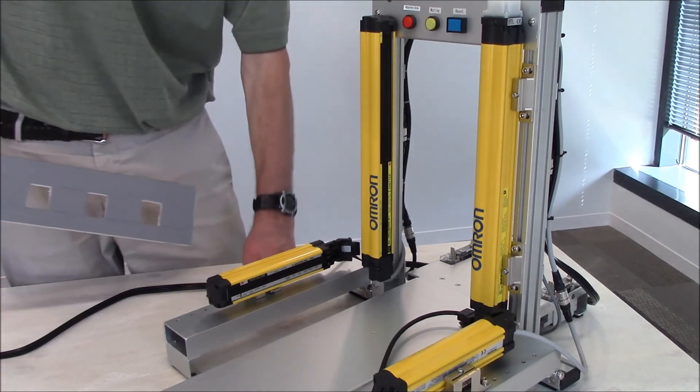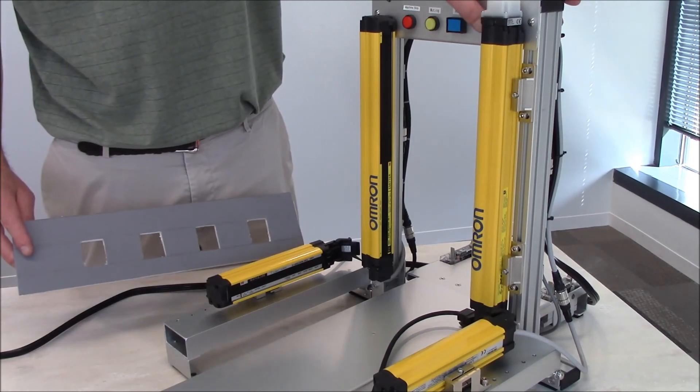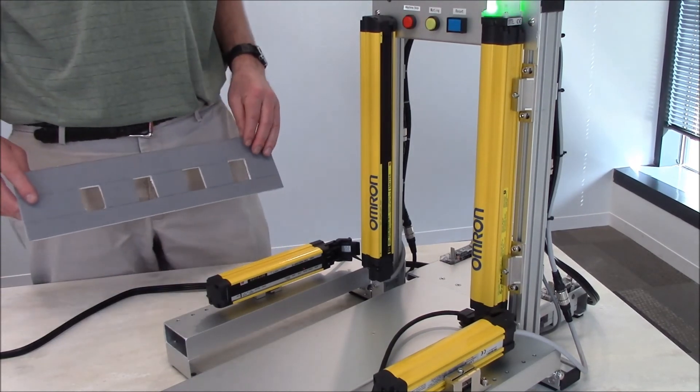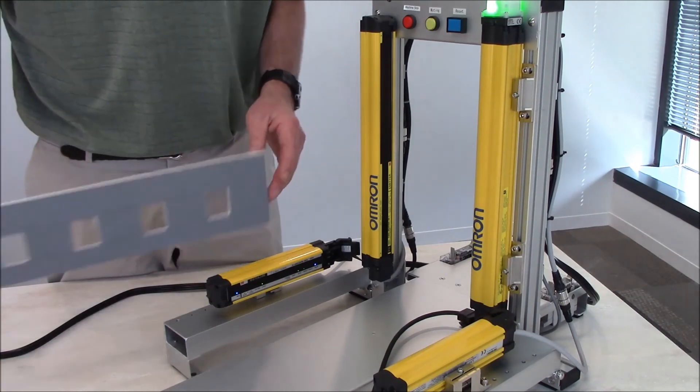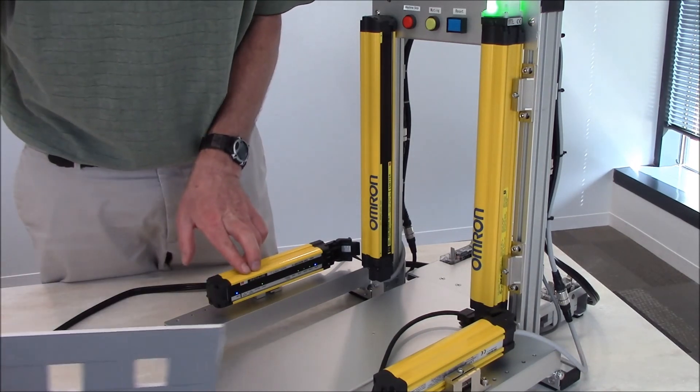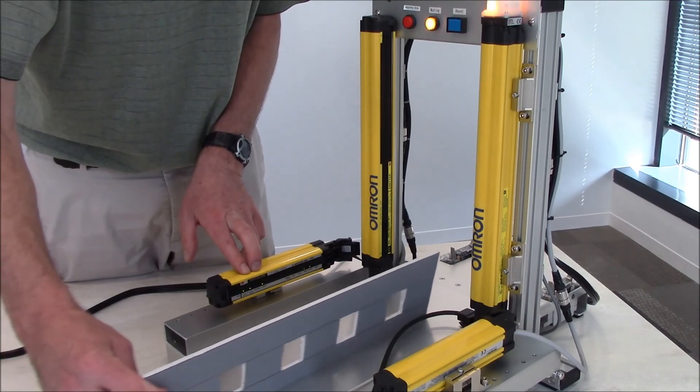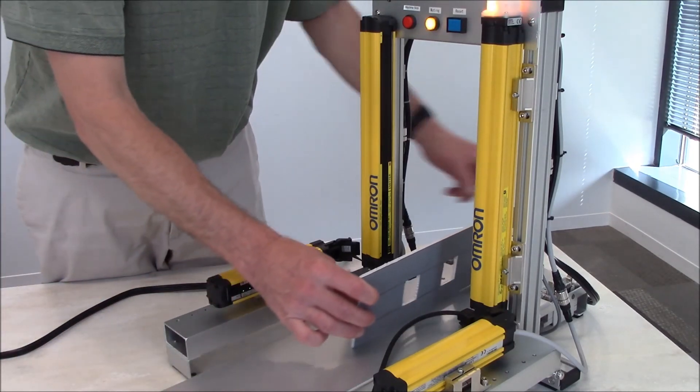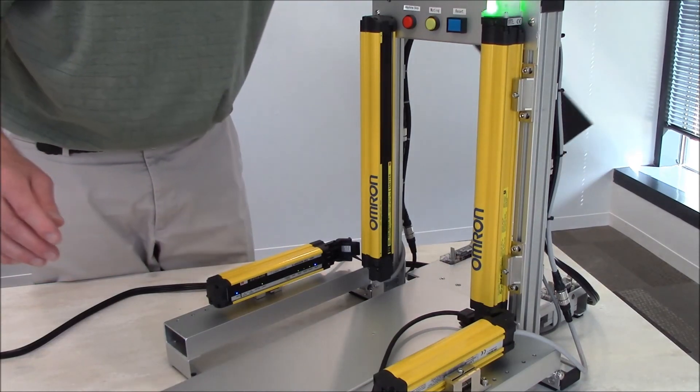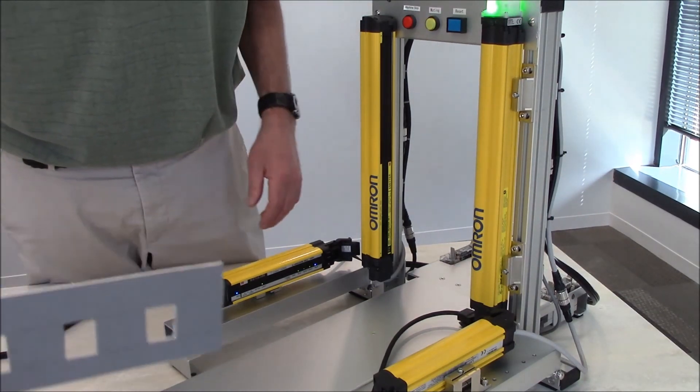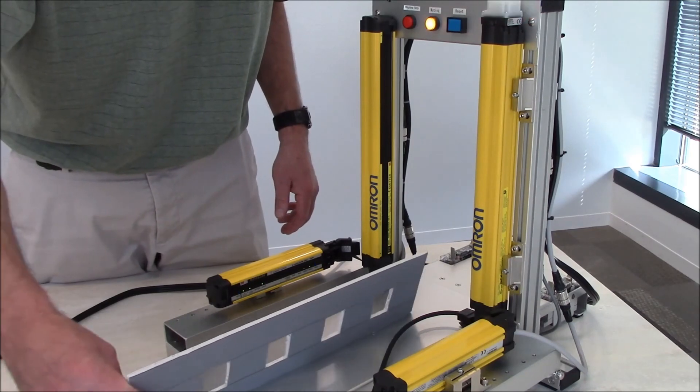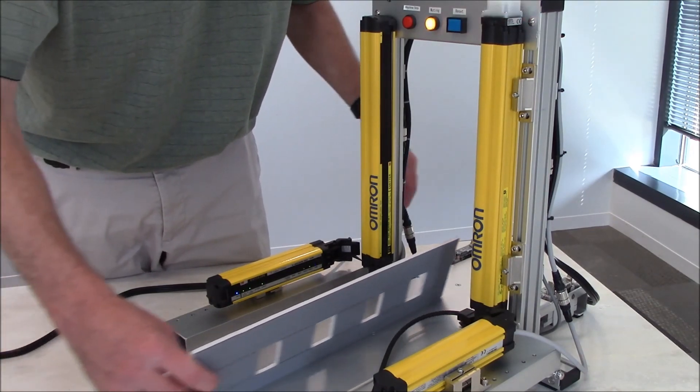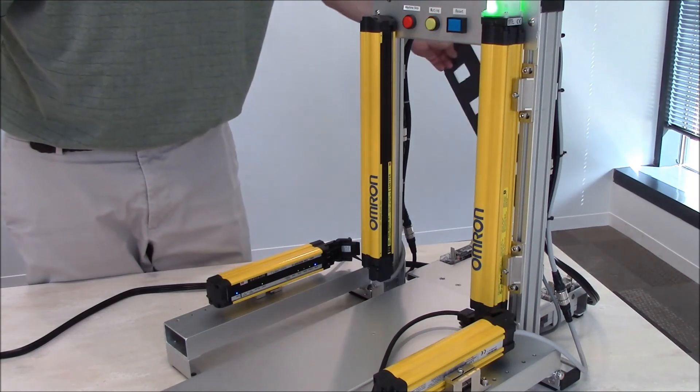Since I turned on dip switch number two, I'm going to turn power on. I'll let it stabilize and now if you watch sensor A and sensor B indications, they're on all the time through the curtain, allowing me to pass the object through. Even if I go back and forth for the anti-chatter, it still goes through with no problem.